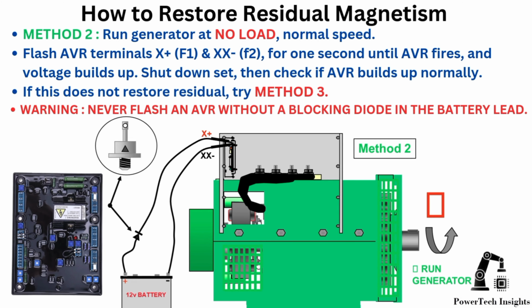Method 2. Run the generator at no load, normal speed. Flash AVR terminals X plus and XX negative for 1 second until the AVR fires and voltage builds up. Shut down the set, then check if the AVR builds up normally. If this does not restore residual, try Method 3. Warning: never flash an AVR without a blocking diode in the battery lead.